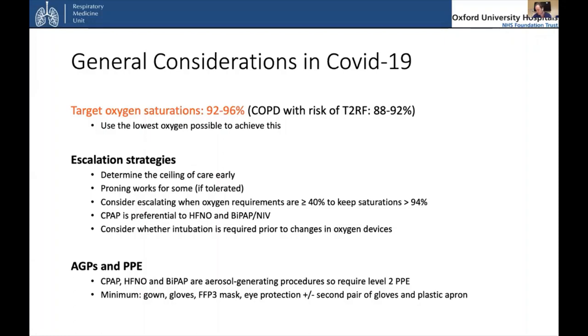And as Chris mentioned, there have been lots of occasions when oxygen levels have dropped in various hospitals and caused significant harm to patients. The risk is not that one device may not work. It's actually that the pressure in the system drops to the point where the ventilators shut off. And so it is important that we are judicious with our use of oxygen.